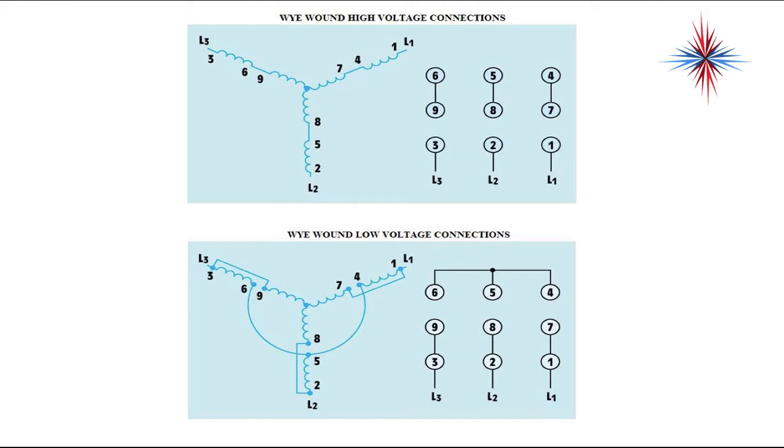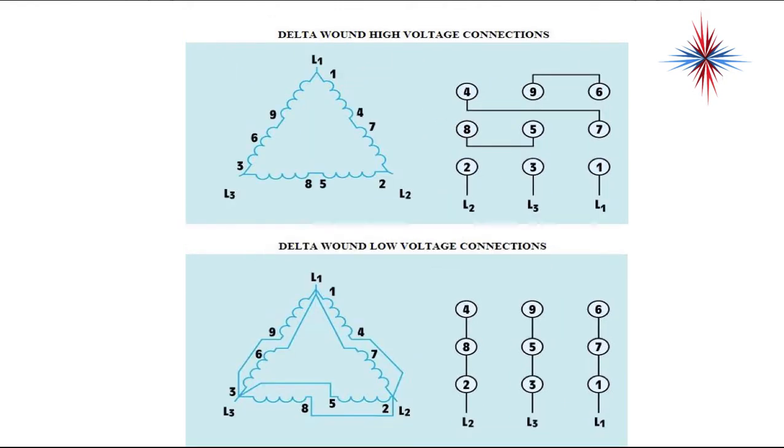These are industry standard. For delta-wound high voltage connections, you're going to wire 5 and 8 together, 4 and 7, and 9 and 6. For delta-wound low voltage connections, you're going to connect 2, 8, and 4; 3, 5, and 9; 1, 7, and 6. And it tells you how you're going to connect your L1, L2, L3.